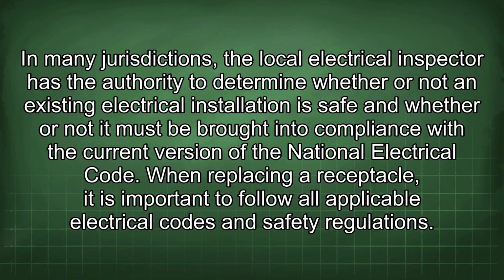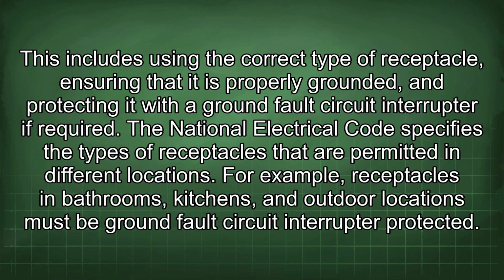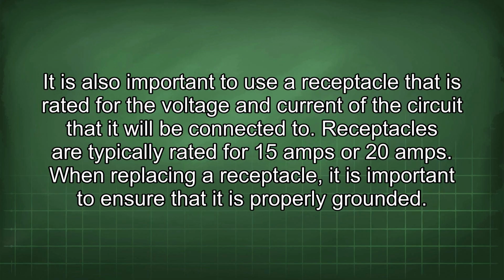When replacing a receptacle, it is important to follow all applicable electrical codes and safety regulations. This includes using the correct type of receptacle, ensuring that it is properly grounded, and protecting it with a ground fault circuit interrupter if required. The National Electrical Code specifies the types of receptacles that are permitted in different locations. For example, receptacles in bathrooms, kitchens, and outdoor locations must be ground fault circuit interrupter protected. It is also important to use a receptacle that is rated for the voltage and current of the circuit that it will be connected to. Receptacles are typically rated for 15 amps or 20 amps.